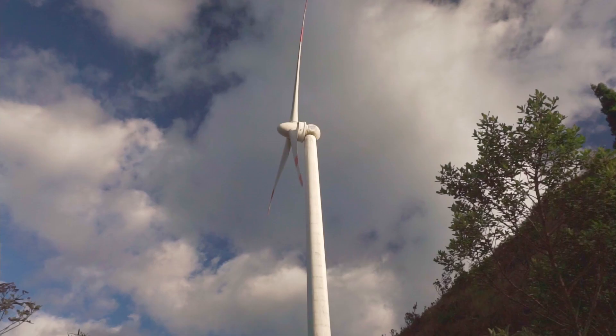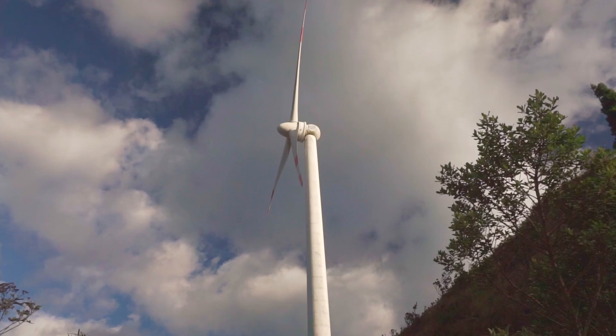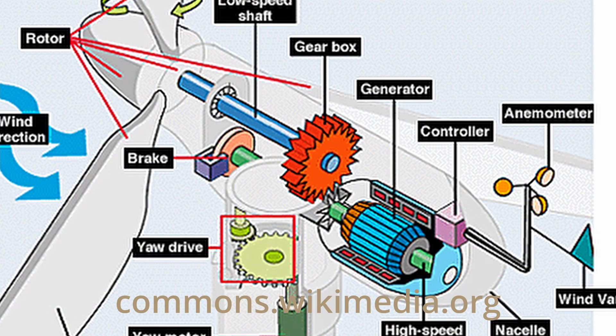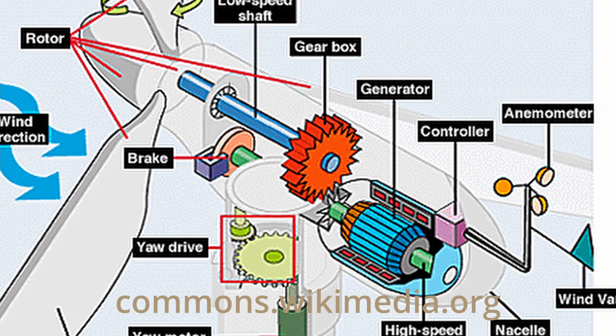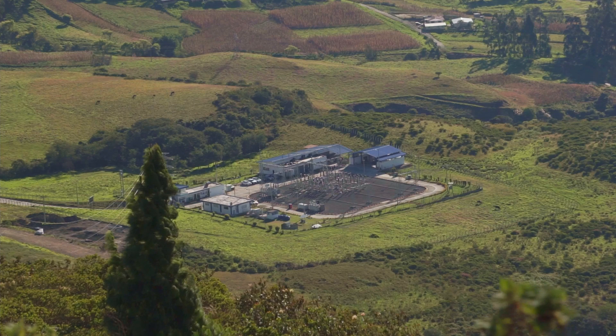The turbines generate electricity by rotating a direct current generator. These particular turbines are connected directly to the generator, whereas others are connected by means of a gearbox. The high amperage DC current produced by the generator is then converted into high voltage AC current, which can be sent to the transfer station. In the case of the Villonaco wind farm, this station is located just down the hill towards the city of Loja. From there, the electricity is transferred to the National Interconnected System for use throughout Ecuador.